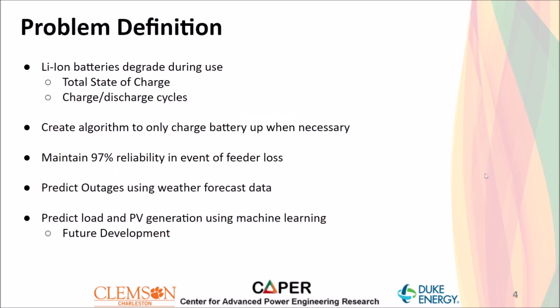The primary problem here is that lithium-ion batteries degrade during their use. The average state of charge is the primary factor of this. The higher the average state of charge, the faster the battery will degrade year to year. Charge and discharge cycles also have an effect, but not as severe. So our goal is to create an algorithm that'll only charge the battery up when necessary.